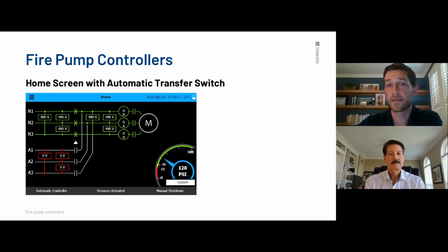Alternate power right now is red. You can see that it says 0 volts. It's just not on. The generator's not running. If the generator was running and it was set up correctly, oh, my drawing's back, and it's set up correctly, then you would have 480 volts here. They would be green. And this icon right here, actually, the way that you can really tell with our screen which power it's being run on, whether it's normal power or alternate power, is going to be this right here, and also these contactors, plus the flow of electricity.